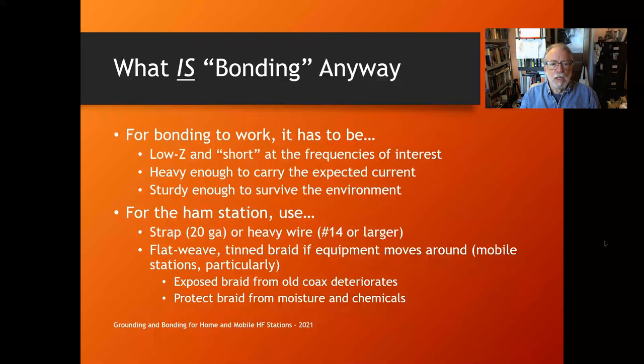For bonding to work it has to be low impedance and electrically short at the frequencies of interest. At 60 Hz, the wavelength is about 5 million meters, so 'short' can be the size of a football stadium. At 2 meters or 40 meters, 'short' is a lot smaller. Otherwise it starts to act like a transmission line, and you don't want that.